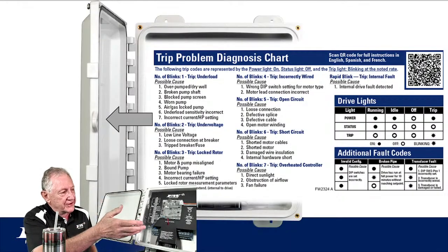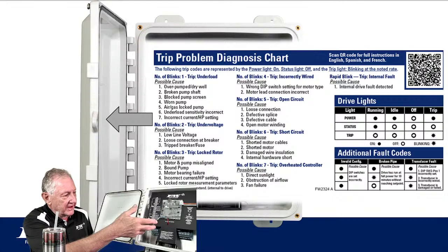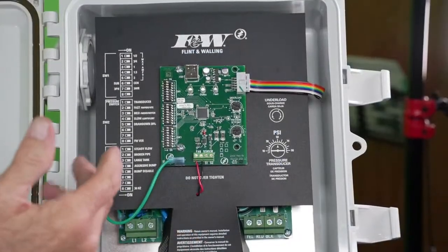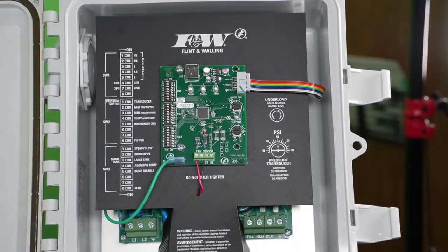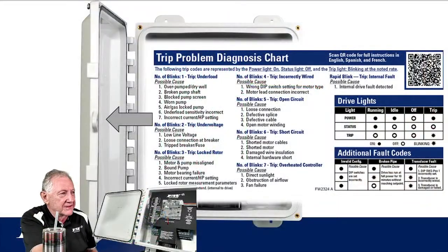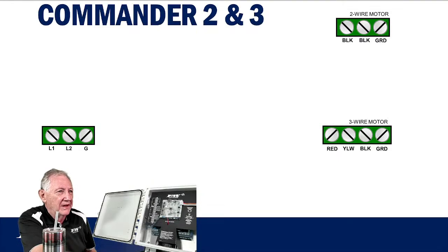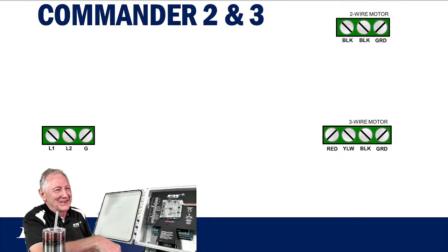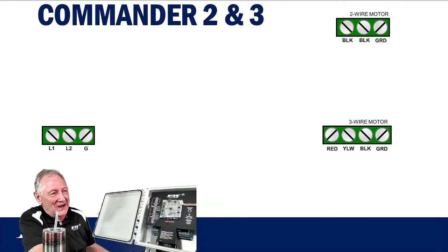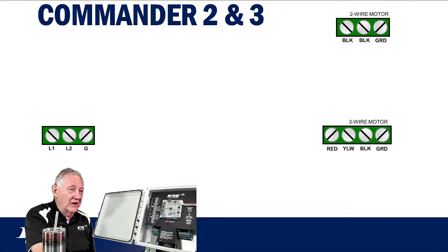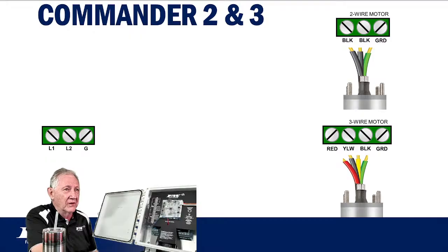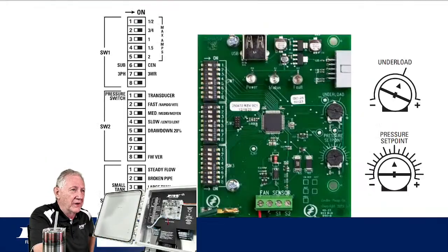So, when we talk about what's new, I've shown you some of the features of this new drive. Now, there are a couple other points here I want to cover on wiring. Let me see if I'm pulling up my next slide. All right, what that slide is basically showing us is that the terminal block for your power, the L1 and L2 on the green ground, is over on the left-hand side. On the right-hand side, the terminal blocks, as I had already mentioned, for a two-wire drive you're only going to have 3 terminals because you only have the 3 wires to hook up, whereas with a 3-wire drive, you're going to have the 4 terminal blocks. So the only difference between those two is the 2-wire motor and a 3-wire motor.